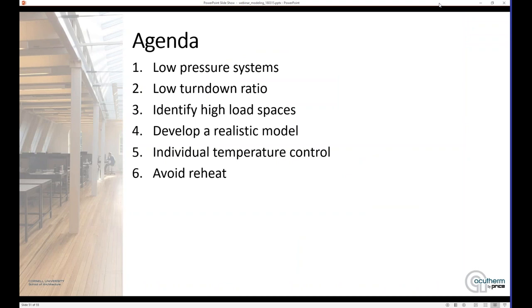So that's our tips for working through energy modeling with Thermafuser diffusers. One, modeling those low-pressure systems by adjusting the horsepower of the fan to accurately show what's being used. Two, working with a low turndown ratio of the diffuser, adjusted under the turndown in the model. Three, identifying those high-load spaces, making sure those are isolated within the model. Four, getting into more realistic modeling by using multiple occupancy schedules and multiple plug-load schedules to create that real-life diversity within your space. Five, further breaking down your model to model that individual temperature control provided by the Thermafuser diffuser. And lastly, avoiding or minimizing the use of reheat as an energy-saving means.